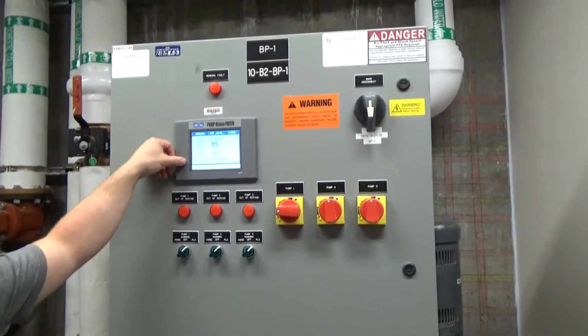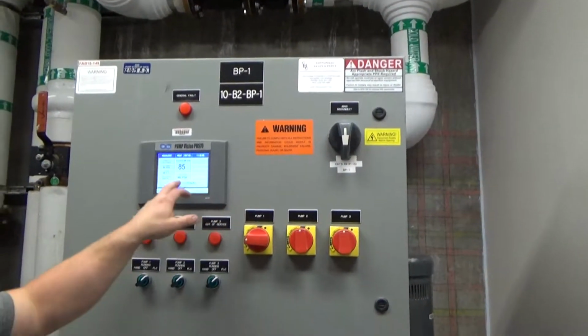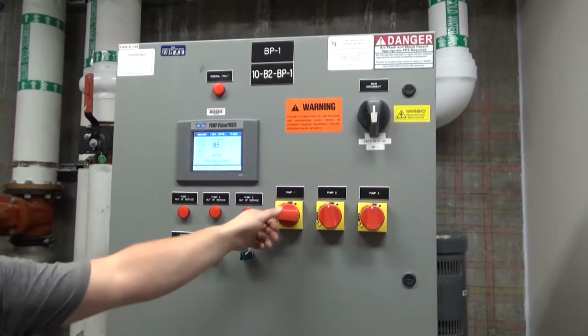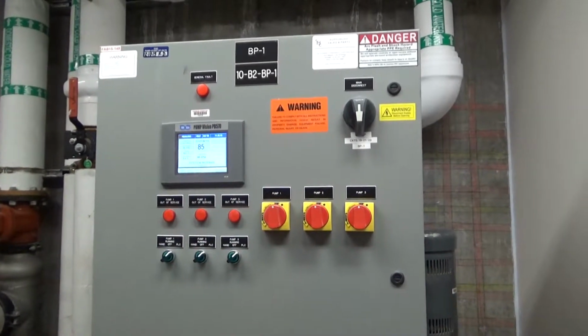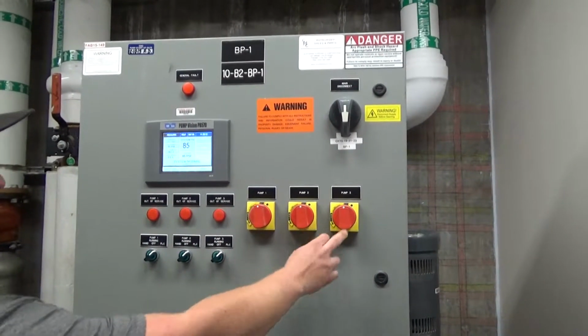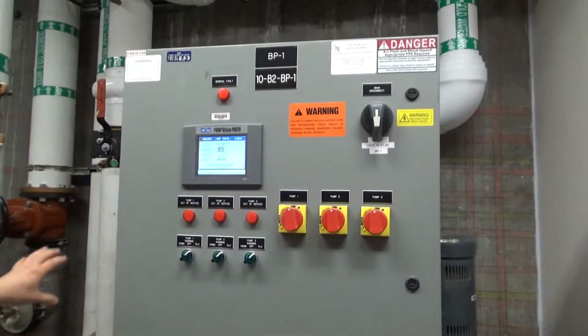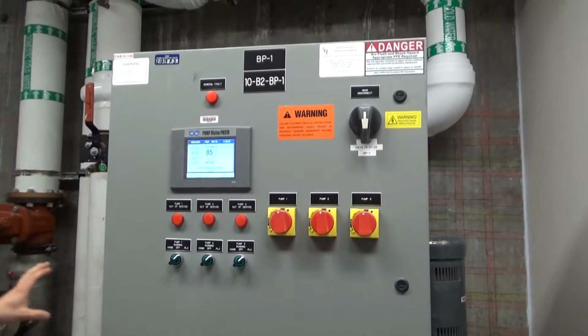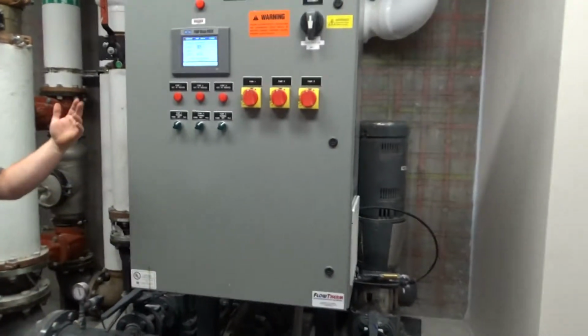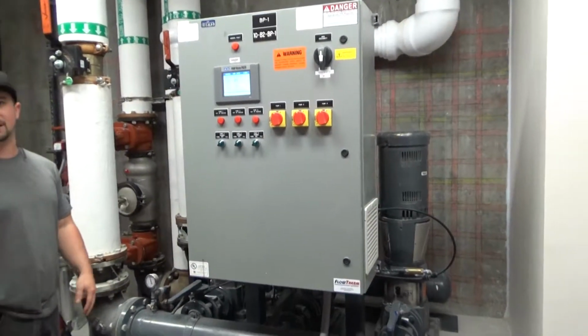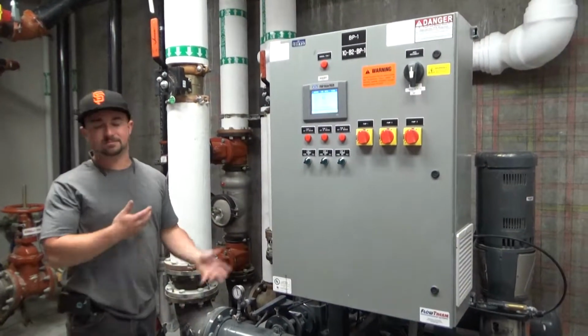And eventually at some point, if it has a call, you'd end up getting a red alert right here. So each one corresponds to a certain pump. Each overload is set to match that amperage on that pump for whatever voltage you have coming in. So if it's 480, there's a certain amperage at 480 that it corresponds to.